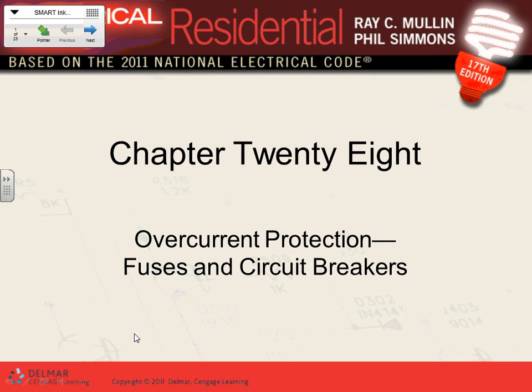The same panel, see that panel right on the wall? If it's a series rated panel, say it's $100. If it's a fully rated panel, it becomes almost $150. Would that make a big difference if that was a panel that's $1,000 and you jump to $1,500? So that's what this chapter is going to talk about, series rated panels and fully rated panels. That's a big concept. Overcurrent protection coordination is a big deal, guys. Let's talk about overcurrent protection coordination.